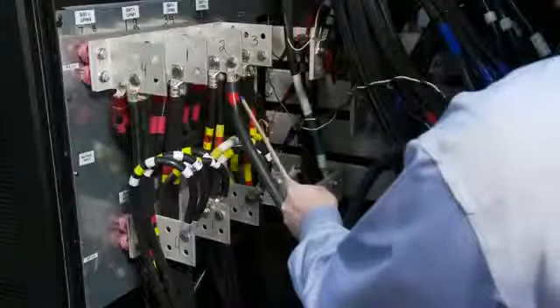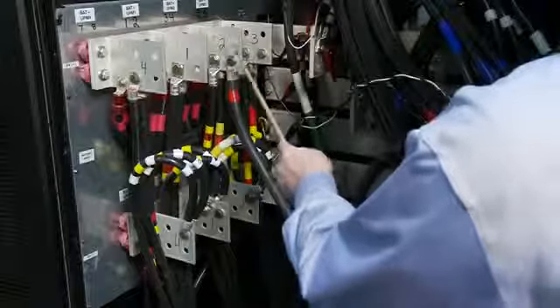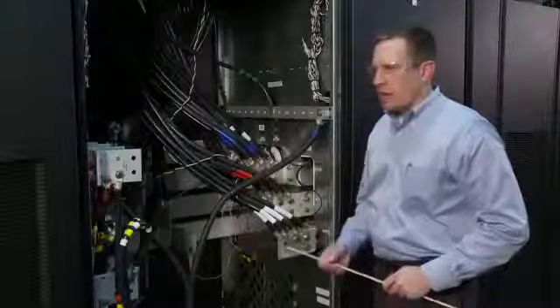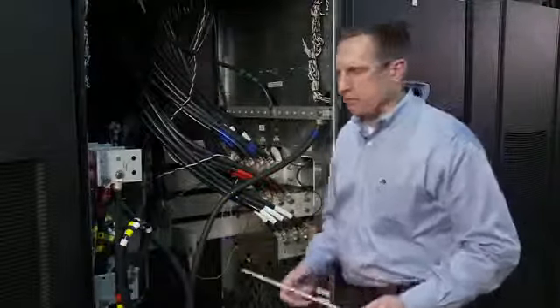As well, you can see that there is a battery plus connection with a wire that follows down to the bottom of the unit, and a chassis ground connection. That wire follows down to the bottom of the unit. These wires follow out around the back to a 1600 amp fault breaker that's to the side of the system.